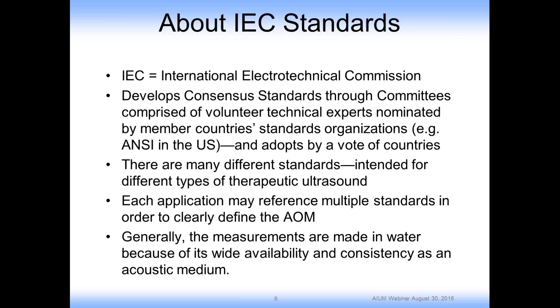There are many different standards for therapeutic ultrasound, and they're designed for different types of therapeutic ultrasound, and we'll be discussing that in a second. It's worth noting that each standard may reference multiple other standards in order to clearly define the acoustic output measurement. And it's also worth noting that generally the measurements are made in water because of water's wide availability and consistency of an acoustic medium. That isn't to say that other mediums couldn't become standardized in the future, but this is just what we have for most of these measurements today.